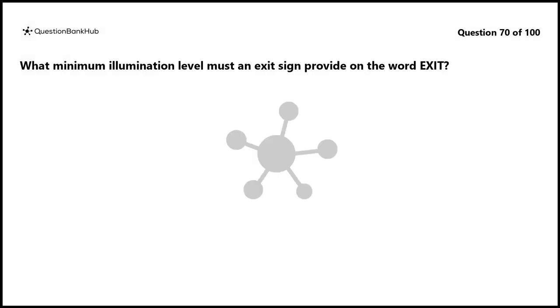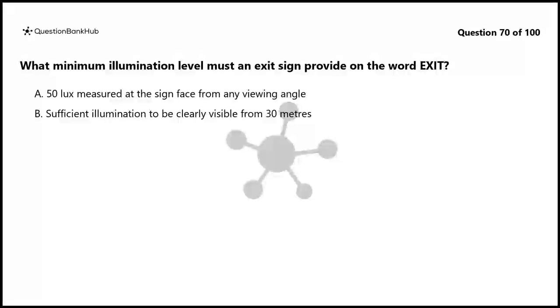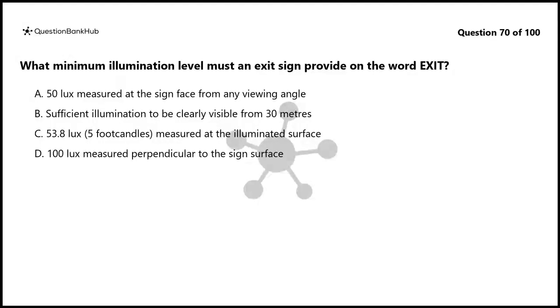Question 70. What minimum illumination level must an exit sign provide on the word exit? A. 50 lux measured at the sign face from any viewing angle. B. Sufficient illumination to be clearly visible from 30 meters. C. 53.8 lux, 5 footcandles, measured at the illuminated surface. D. 100 lux measured perpendicular to the sign surface.